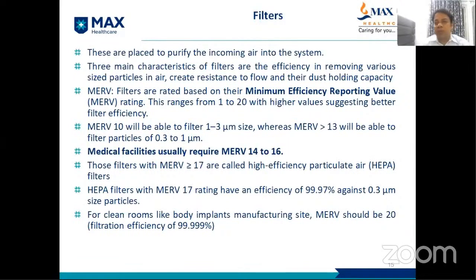Now the filter is most important, and filters are placed to purify the incoming air into the system. The three main characteristics of filters are efficiency in removing various size particles in air, resistance to flow, and dust holding capacity. Filters are rated based on the minimum efficiency reporting value, that is the MERV rating. These range from 1 to 20, with a higher value suggesting better filter efficiency. MERV 10 will be able to filter 1 to 3 micron size, whereas MERV more than 13 will be able to filter particles between 0.3 to 1 micron size.